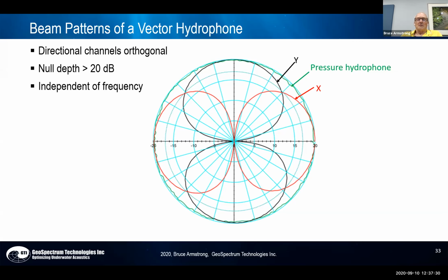The beam pattern of a vector hydrophone looks like this. So you've got the X and Y channels. Those are cosine patterns. So you have a maximum along one axis, and at 90 degrees to it, you have a minimum. And you have 2 channels, an X and Y channel in this case. And the null depth should be at least 20 dB. And this pattern should be independent of frequency. At 5 hertz, you should be getting the same pattern as you do at 2 or 3 kilohertz. In a vector hydrophone, you also have a pressure hydrophone, the one that we've been talking about, and its pattern is omnidirectional, which is why they're sometimes called omnis.